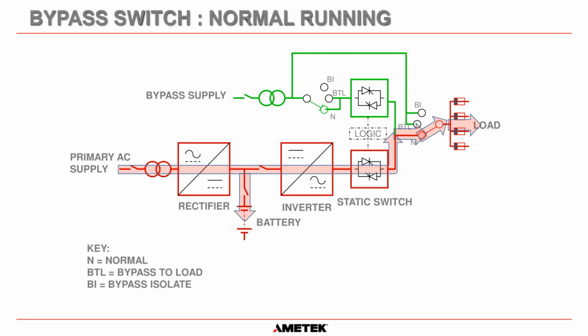The contacts are designed to be make before break. So when you move from one position to the next, it gives you a seamless transfer without any break in supply. But it is mechanical, so there is the opportunity for the contacts to fail at some point, but they're usually very robust. In normal operation, with the bypass switch in the normal position, power will flow from the UPS through this normal contact and out to the load. And you can see we also have this normal contact here. So bypass supply is allowed to flow through and is ready at the static switch, but this static switch is off because it's not required at this time.